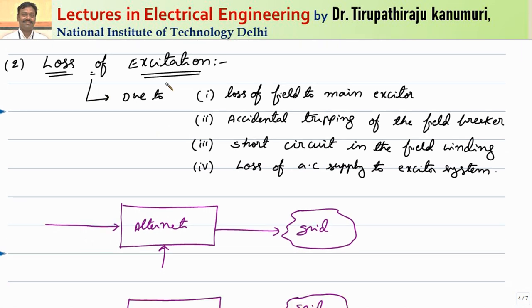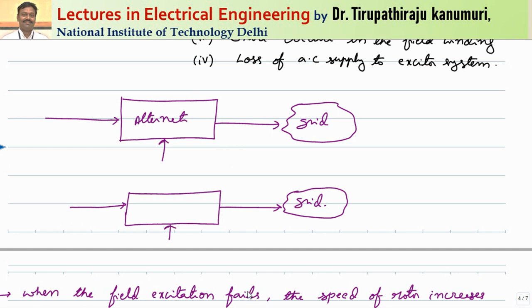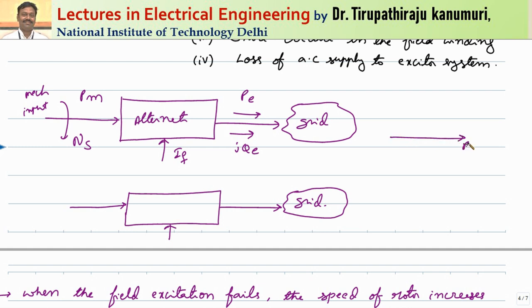The next problem is loss of excitation. Loss of excitation can happen due to loss of field to the main exciter, accidental tripping of the field breaker, short circuit in the field winding, or loss of AC supply to the exciter system. Normally, the mechanical power rotates the alternator at speed NS, the field supply IF is there, and the alternator supplies both active and reactive electrical power to the grid, acting as a generator. But if the field excitation fails, IF becomes equal to zero while the mechanical input remains the same.